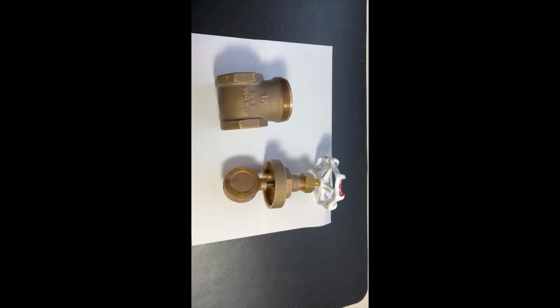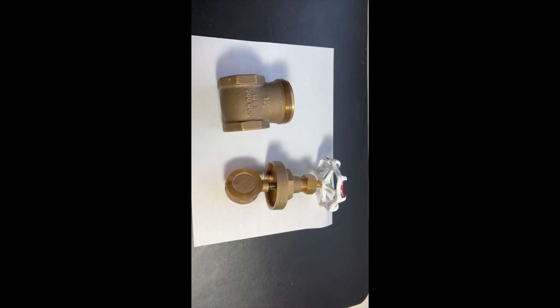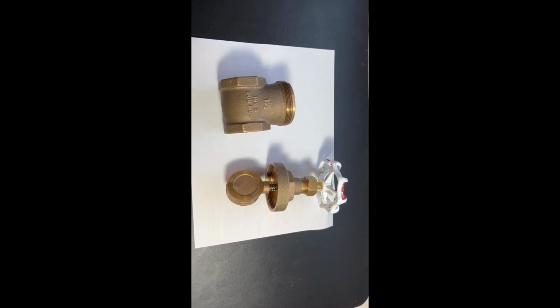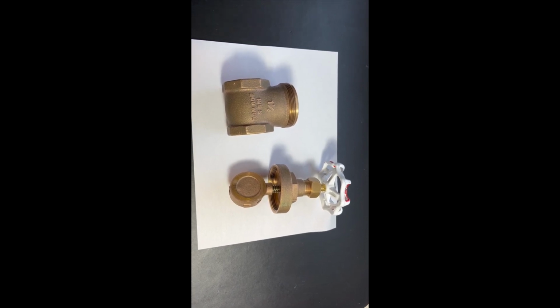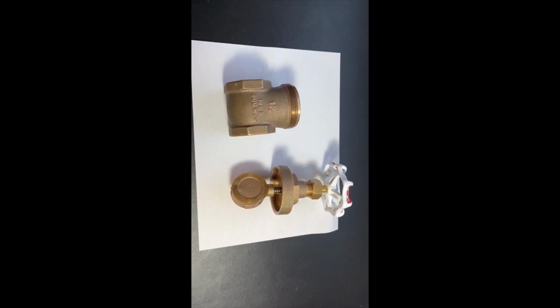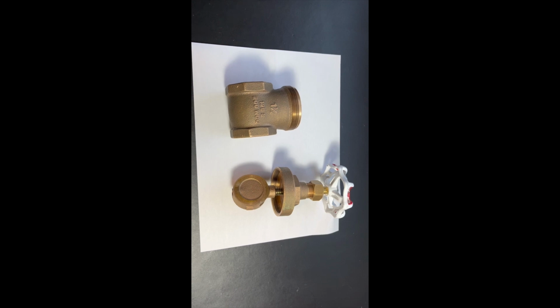They are ideal for turbulent flows because there are no loose internal parts to vibrate and wear. Wide variations in temperature will cause the body to pinch the disc in the closed position. To overcome this, use a flexible wedge disc. A flexible wedge disc is hollow around the edges and solid across the center portion. This gives it some flexibility to prevent pinching.